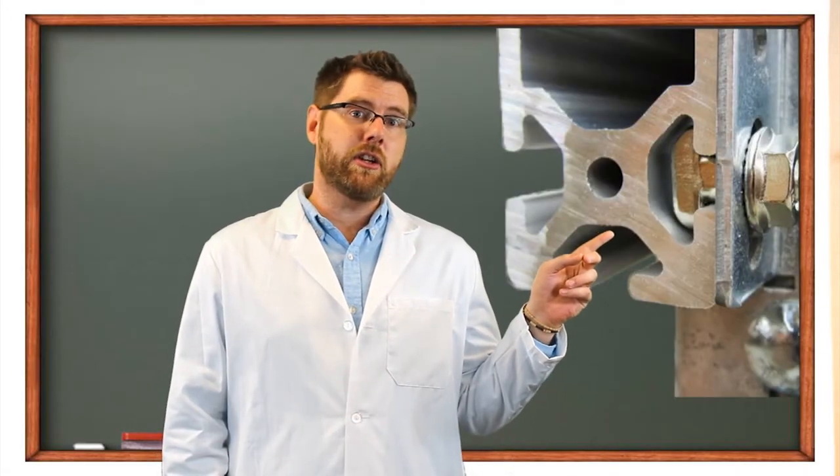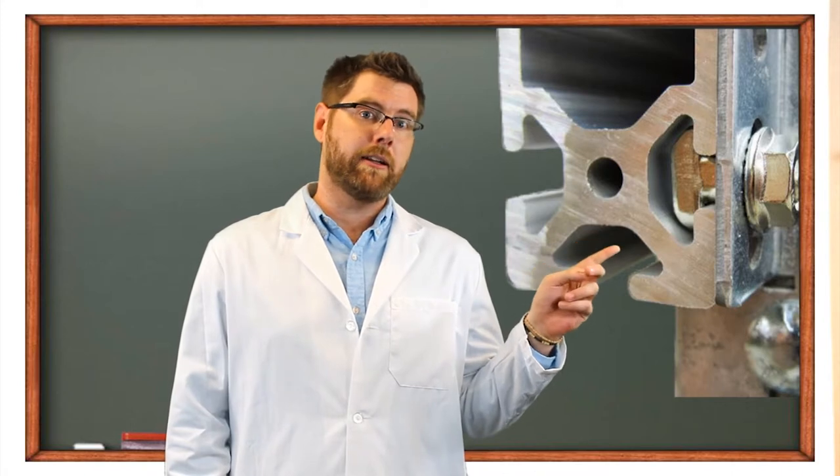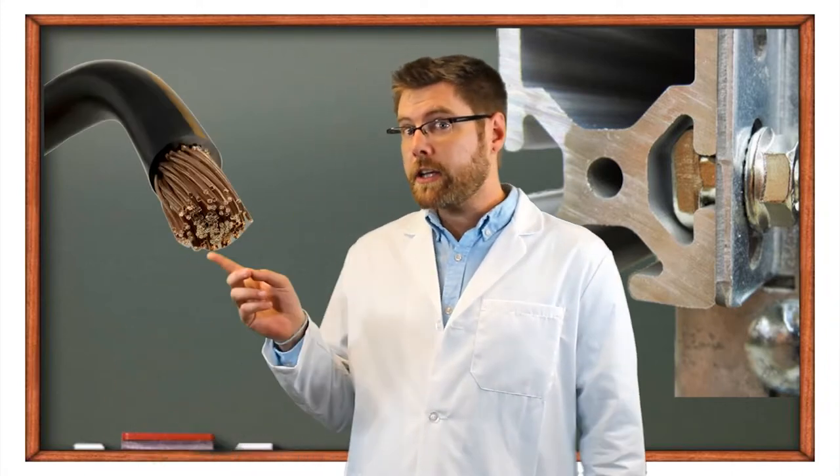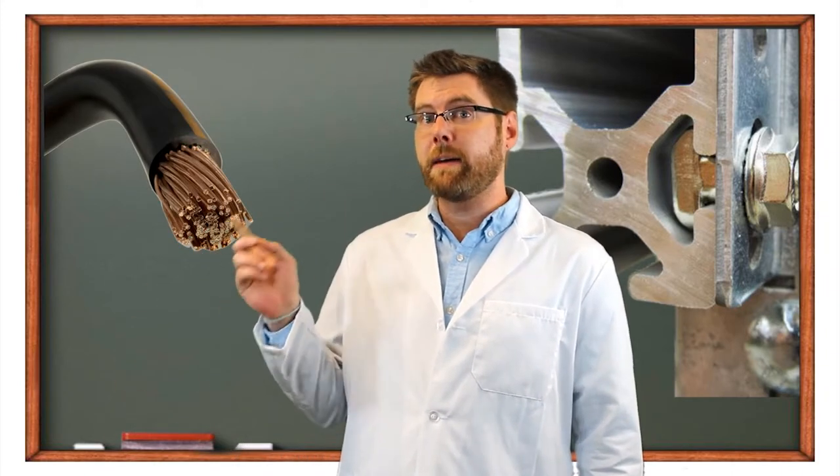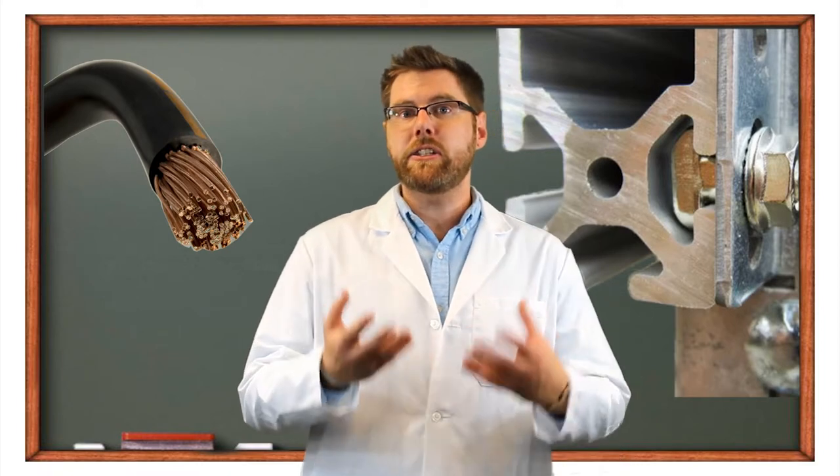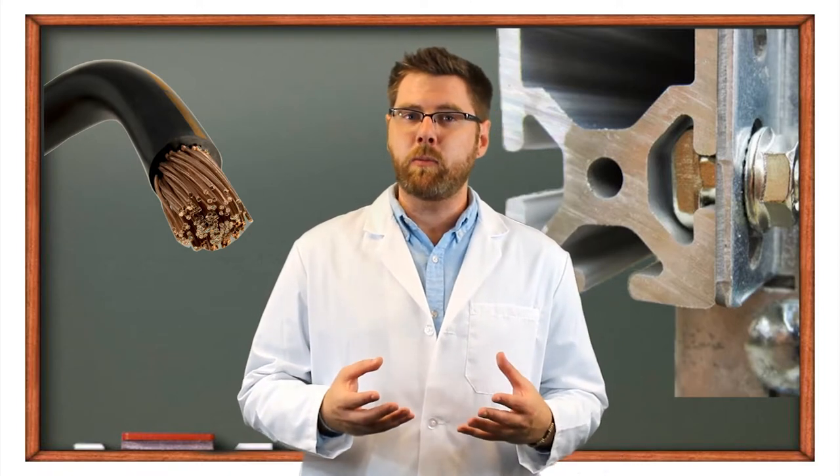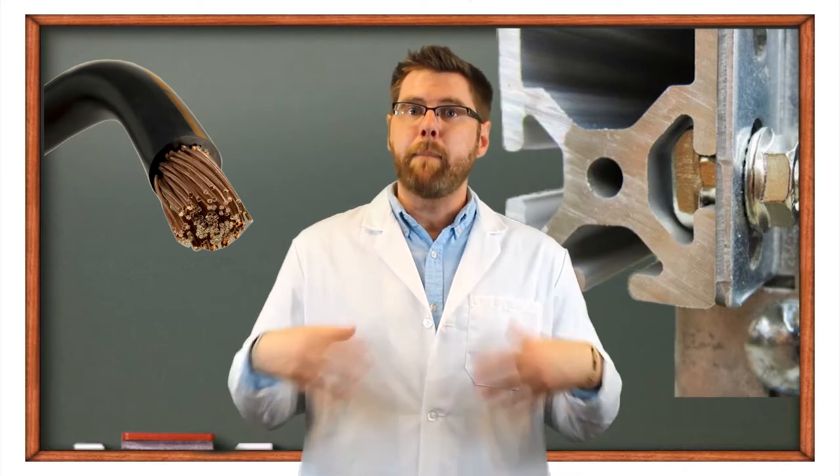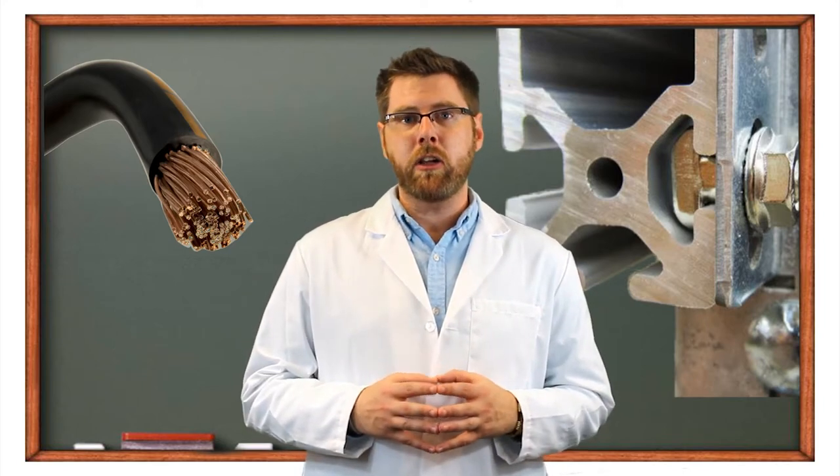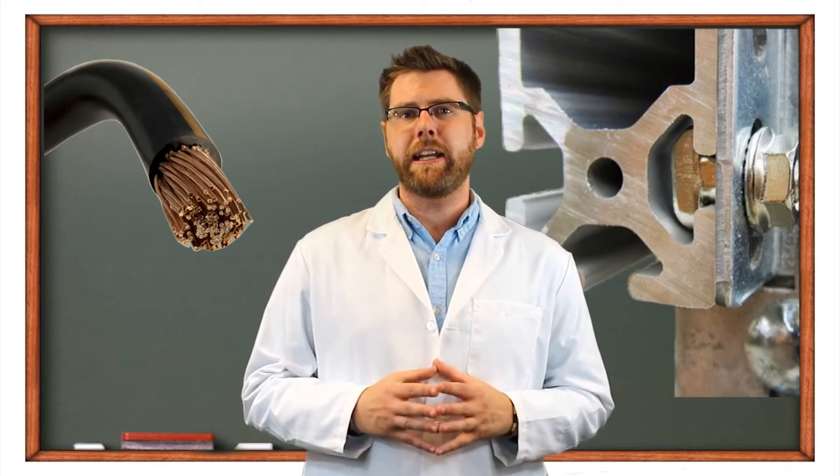This is the cross-sectional area of a typical aluminum rail. This is the cross-sectional area of a number six gauge copper ground conductor. Since the cross-sectional area of the aluminum rail is so much bigger, bonding to an already grounded rail creates a much better electrical connection.